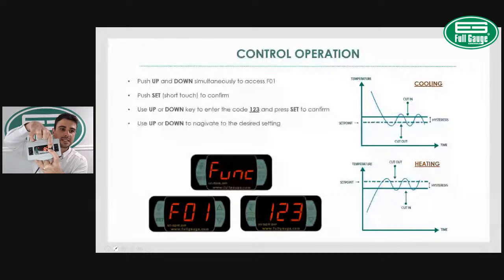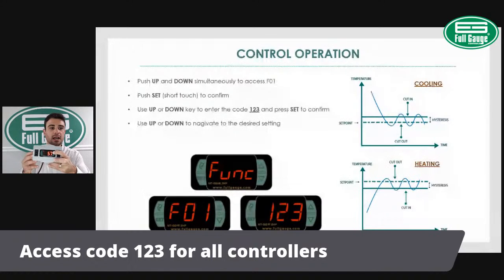Once you push up and down simultaneously, it takes you to function F01. When you are at F01, you press set to confirm, and then you use the up or down keys to go through to the code 123. We are looking for the code 123, and that's the access code for all the control parameters. Once we enter 123, press set again to confirm, and here we are: function 1, 2, 3, and so forth.